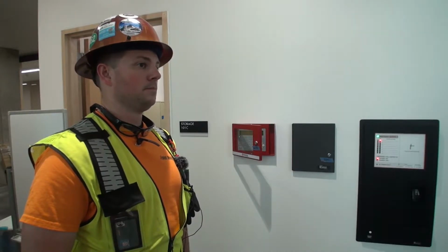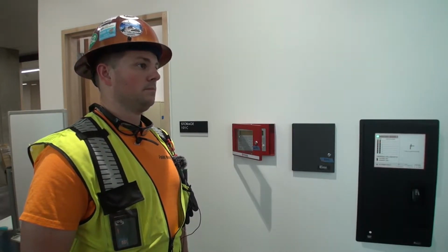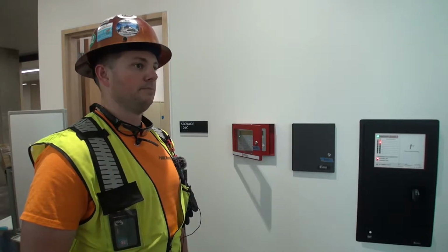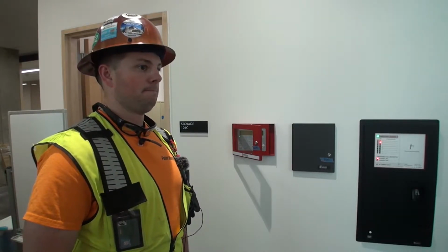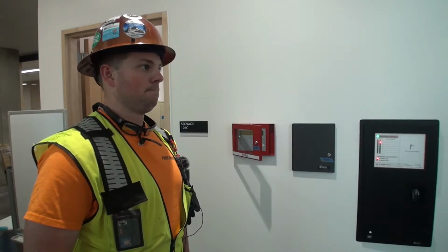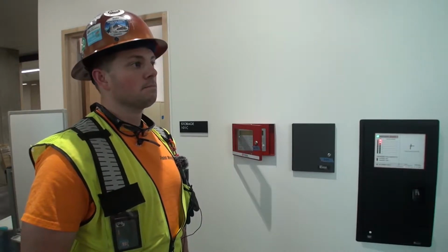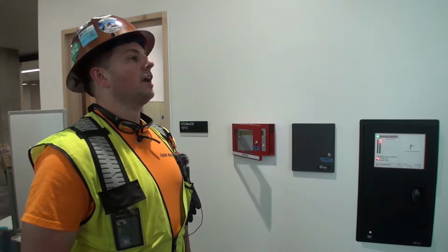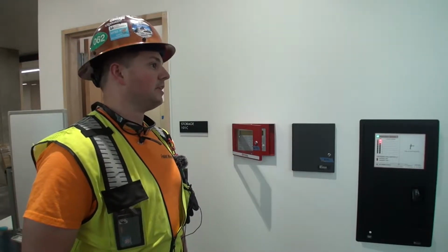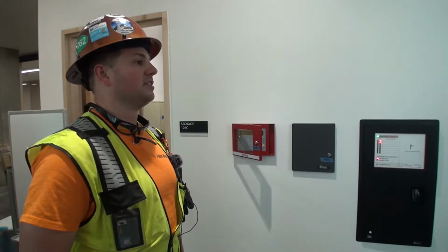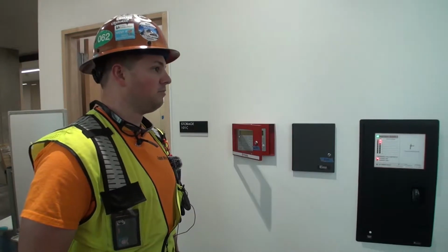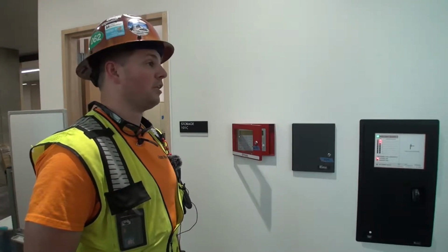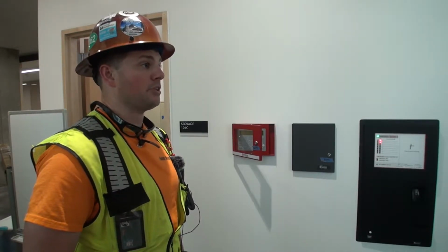So when the system shuts down, do the dampers delay before they close, or do they close immediately? They close. There's no zoning to the duct detection or doors or anything like that. It's just full general alarm. A duct detector activates unit shutdown and fire smoke dampers, and I believe it also drops all of the doors per the operational matrix.